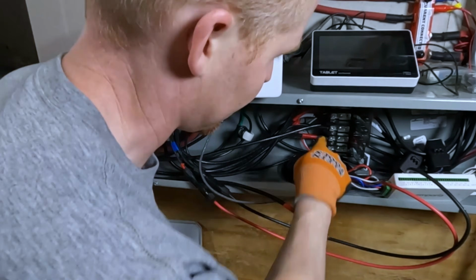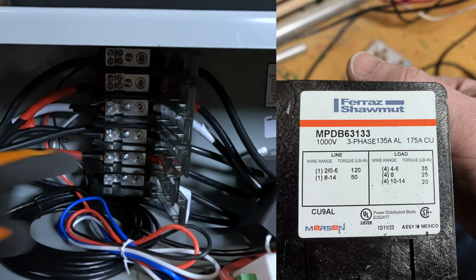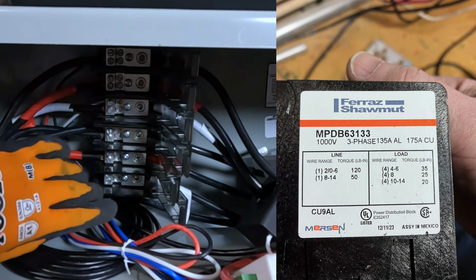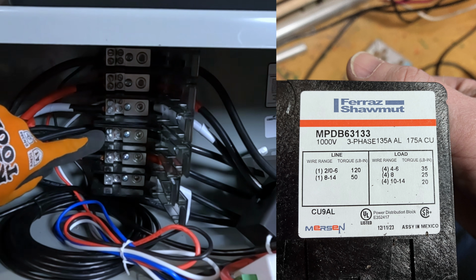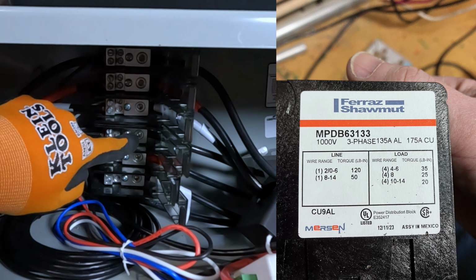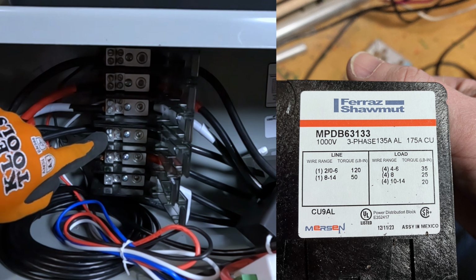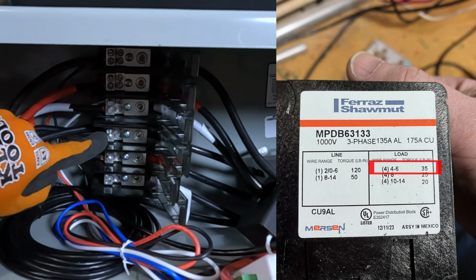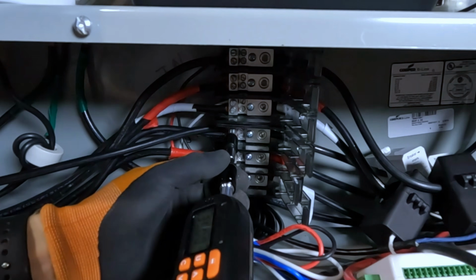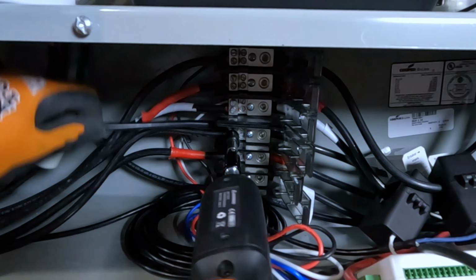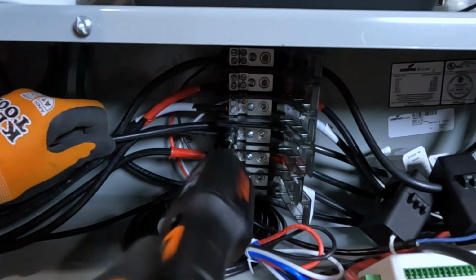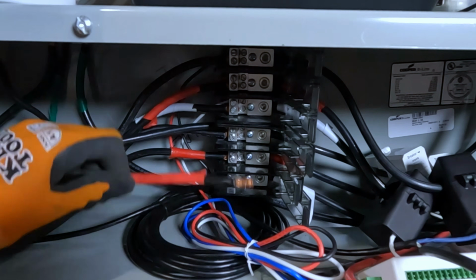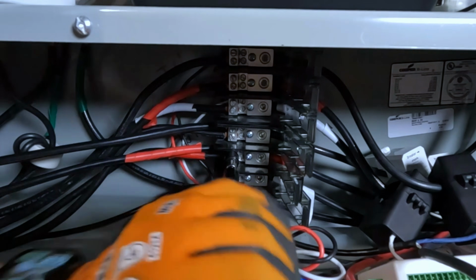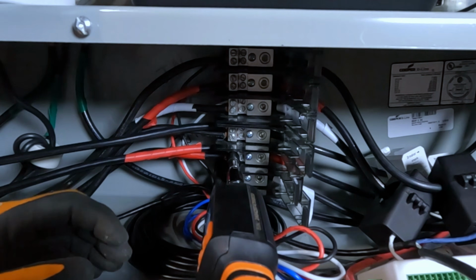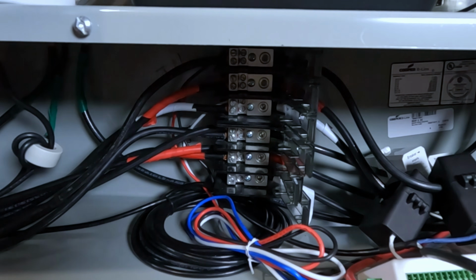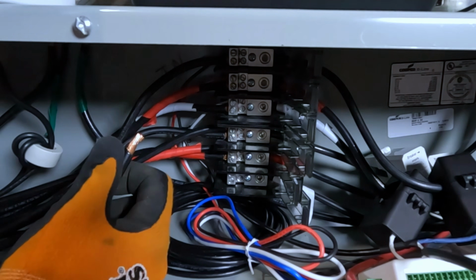And then I just looked at a picture of the torque rating of these. And so thankfully, the load side of these PDBs, which the left side with multiple terminals is the load side. This is actually, they refer to this as the line side. The load side torque spec for a 4 gauge wire is 35 inch-pounds as well. So thankfully, I don't have to make any adjustments on my torque wrench. So there's my line 1. And line 2. And since we're already down here on this side, let's add the neutral.